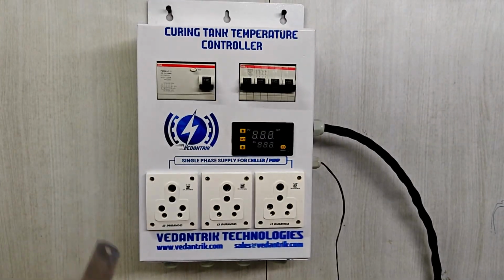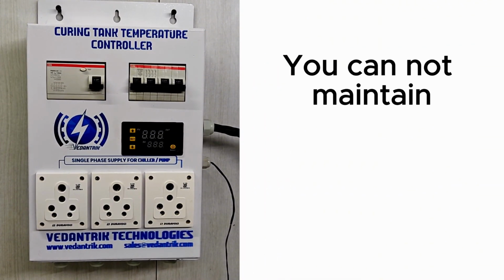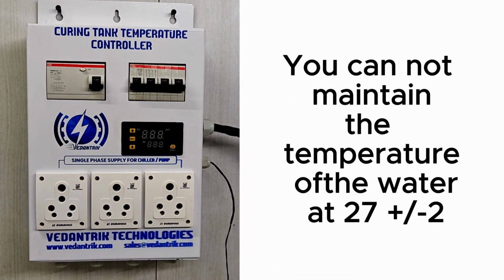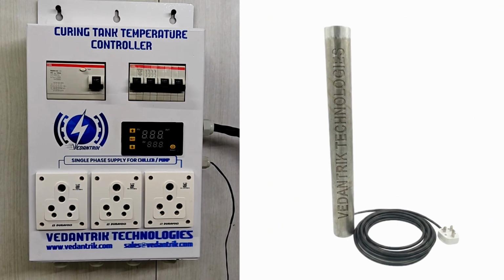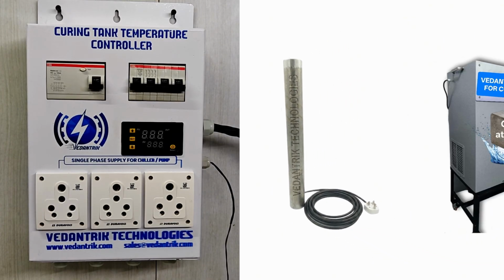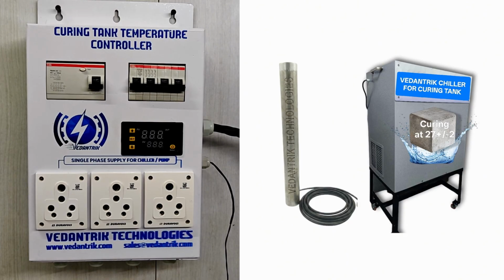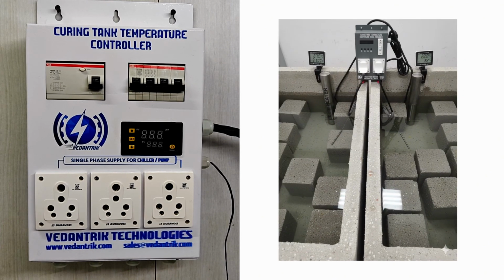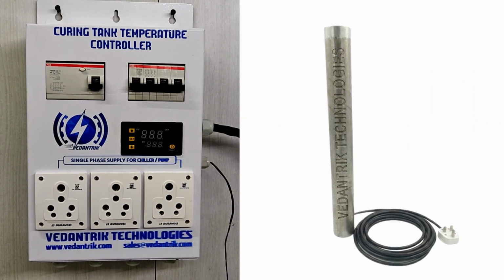Only using this curing tank temperature controller, you cannot maintain the temperature of the water at 27 plus minus 2. You would require a heater which will heat the water's temperature, and you would require a chiller which will chill the water's temperature. So this is just a curing tank temperature controller. This will control your heater or chiller.